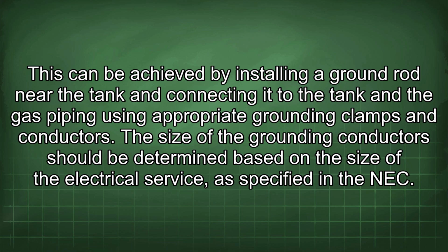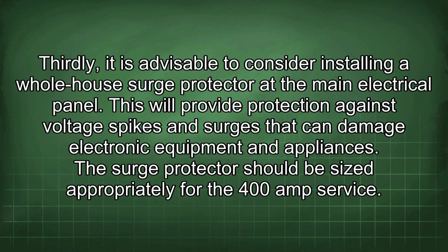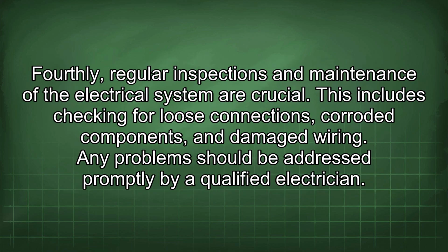The size of the grounding conductors should be determined based on the size of the electrical service, as specified in the NEC. Thirdly, it is advisable to consider installing a whole house surge protector at the main electrical panel. This will provide protection against voltage spikes and surges that can damage electronic equipment and appliances. The surge protector should be sized appropriately for the 400 amp service. Fourthly, regular inspections and maintenance of the electrical system are crucial. This includes checking for loose connections, corroded components, and damaged wiring. Any problem should be addressed promptly by a qualified electrician.